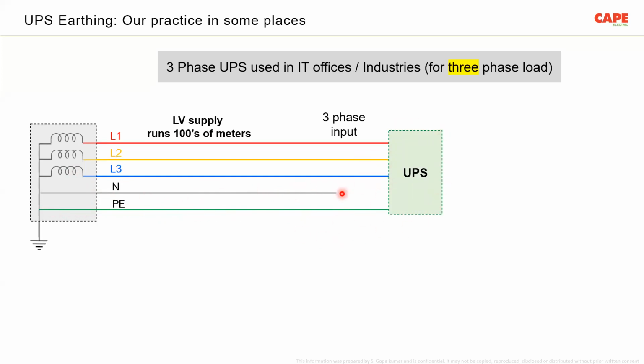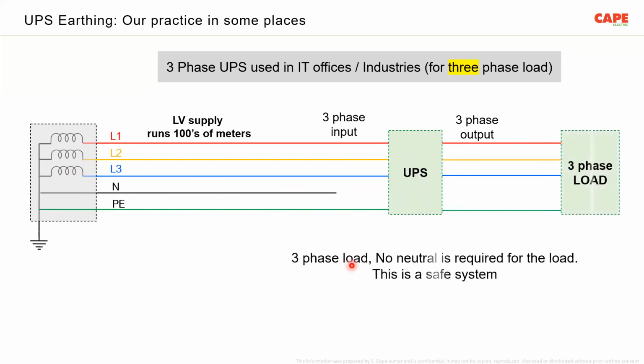Now you look at the UPS. The UPS is a 3-phase input and 3-phase output. So R, Y, B goes inside the UPS and it has got an output R, Y, B phase. And now, if the load is 3-phase, this circuit is perfect. Remember, if the load is 3-phase, because your UPS output is 3-phase, you can connect it to your load and things work perfectly. This is a safe system.